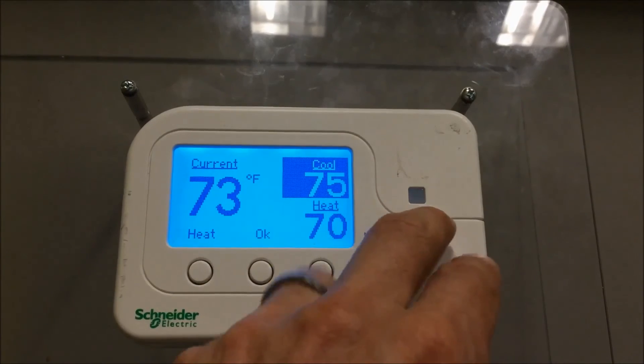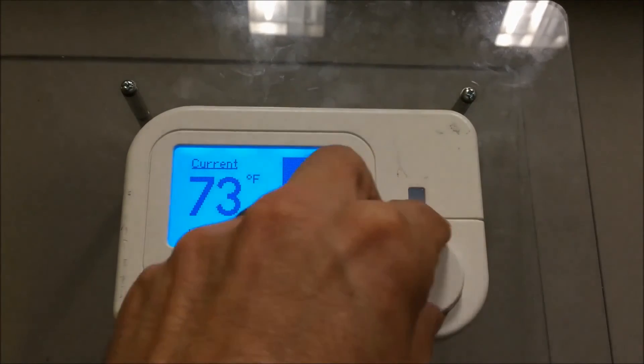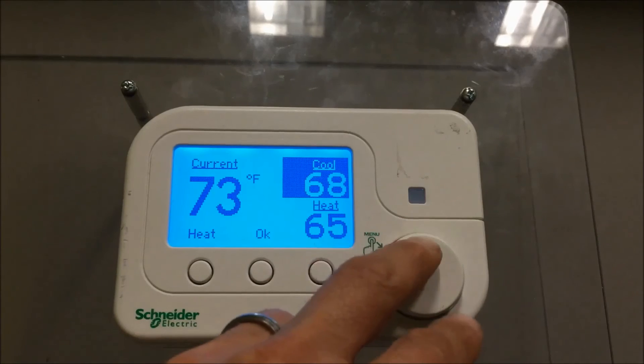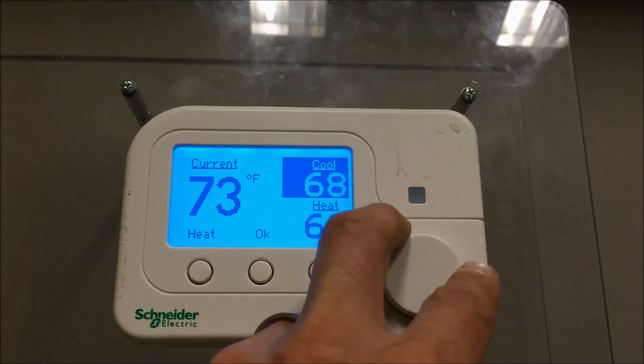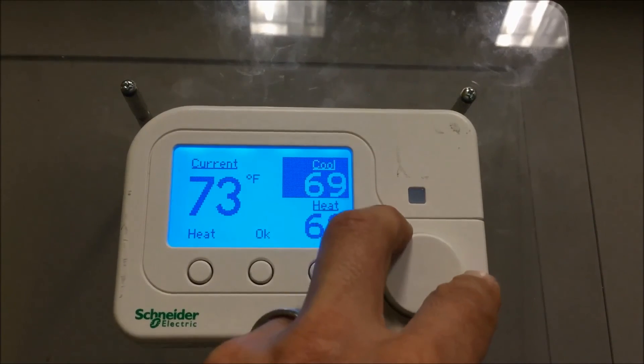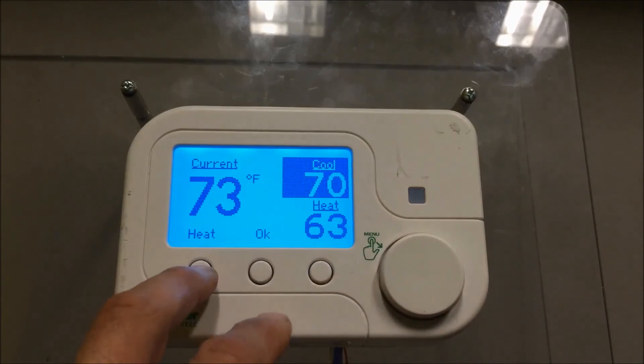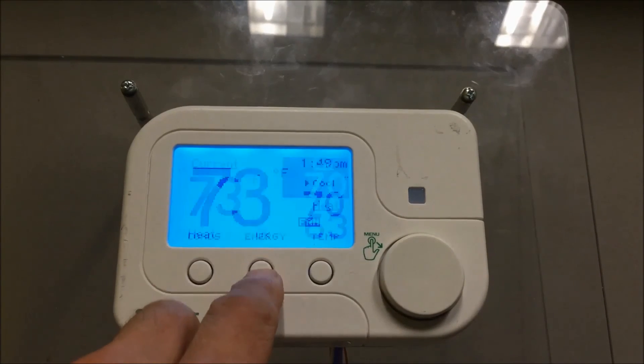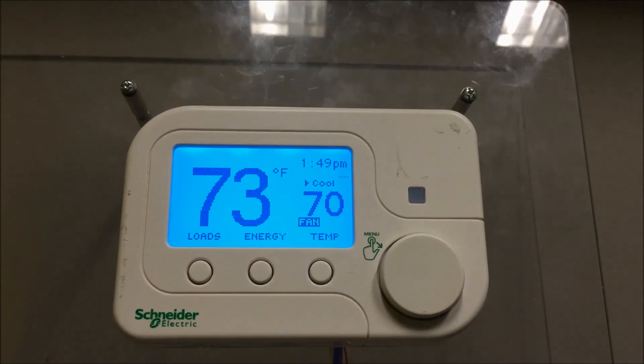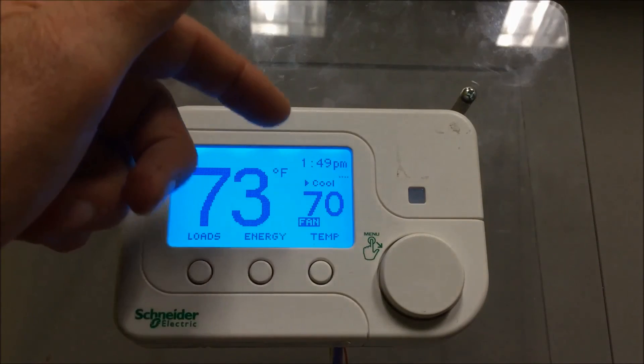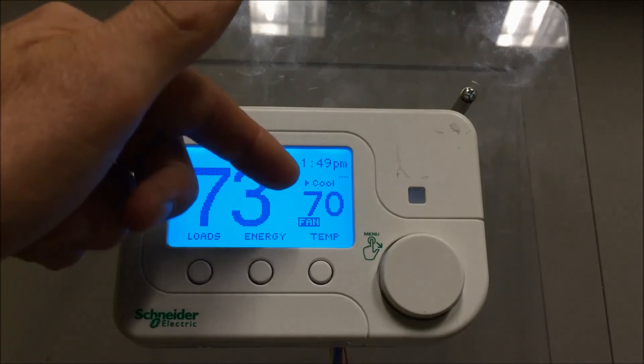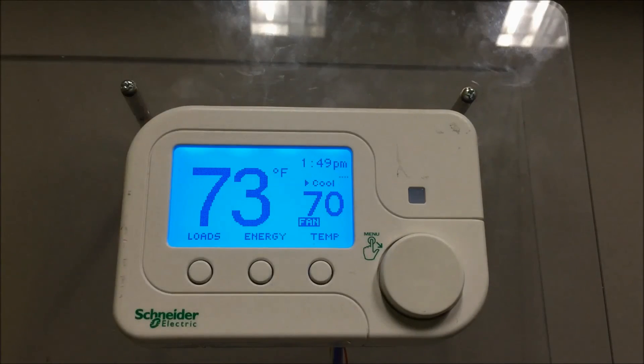Since I'm in auto mode it's going to force at least a 3-degree difference between the heat and cool — it has to have a dead band. So I'm at 73 degrees in the space right now, but I set my set point to 70, so it kicked on cool and the fan. The fan is running and the triangle next to cool means it turned on the air conditioning system.